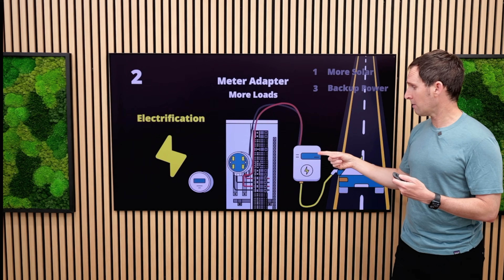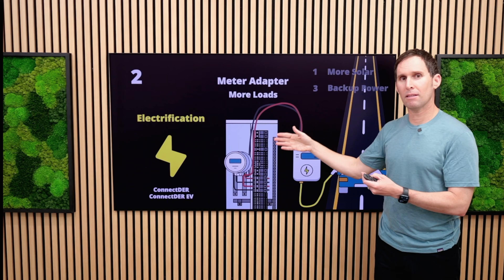Because what's happening is you now have two flows for electricity — one going to the main bus and another going directly to this EV charger. And because it's before the main breaker even, you can effectively avoid the limit that the main bus bar had before. You now basically have another highway for the electricity to travel. The manufacturer I know that currently has this available is, again, ConnectDER.